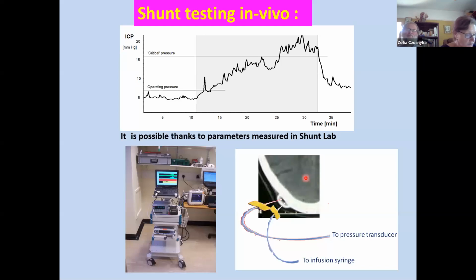Our methodology of in vivo shunt assessment is based on our experience in studying CSF dynamics and data from the shunt laboratory. The method uses an infusion test and appropriate interpretation of the results. Most shunts have a pre-chamber, which allows us easy access to CSF space. Two butterfly gauge 25 needles can be inserted, one for measurement, one for infusion.